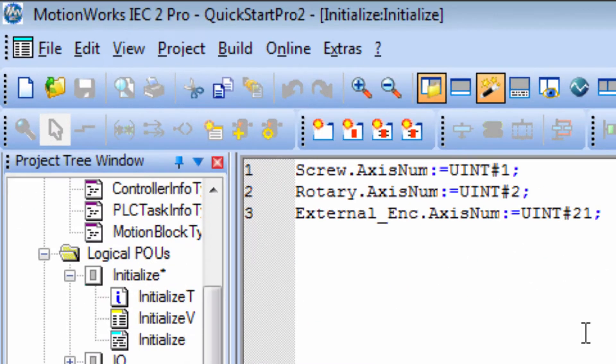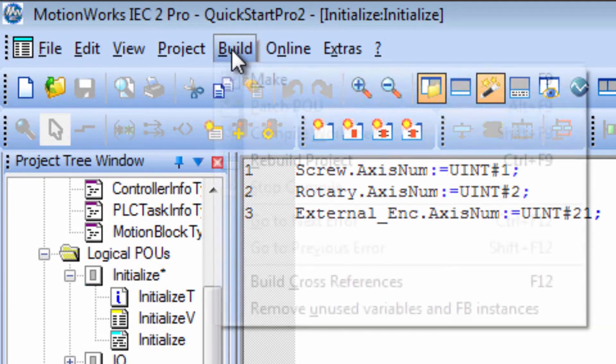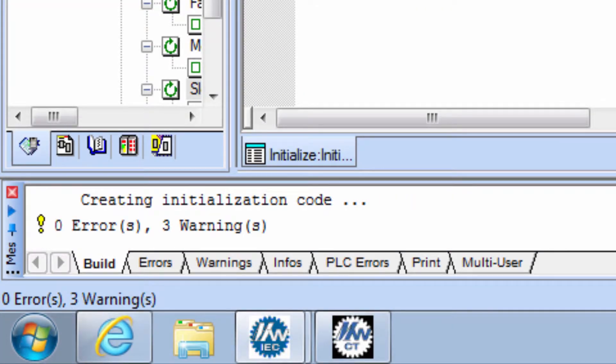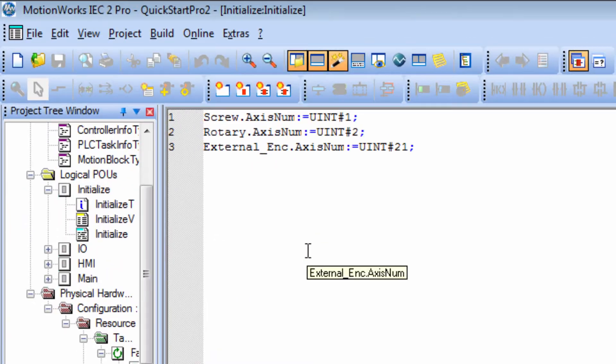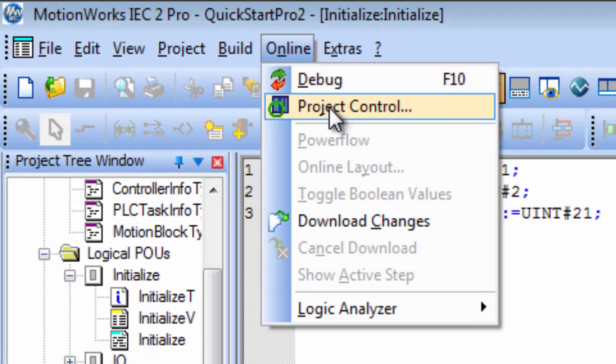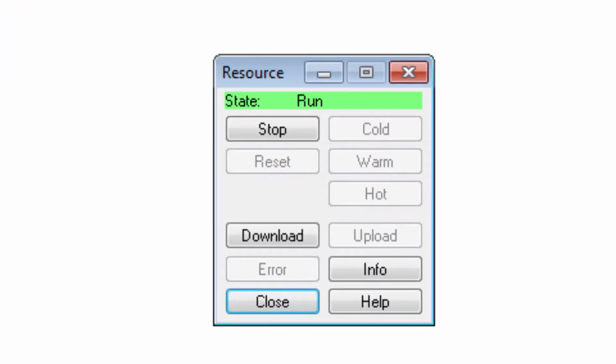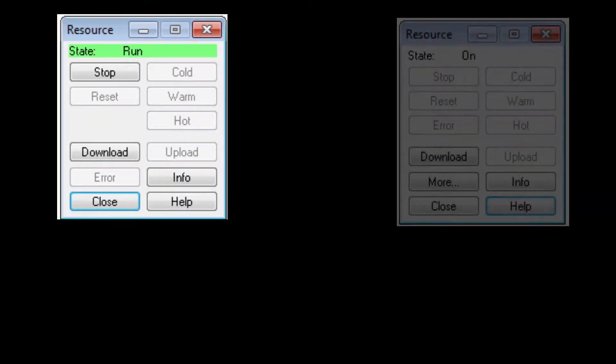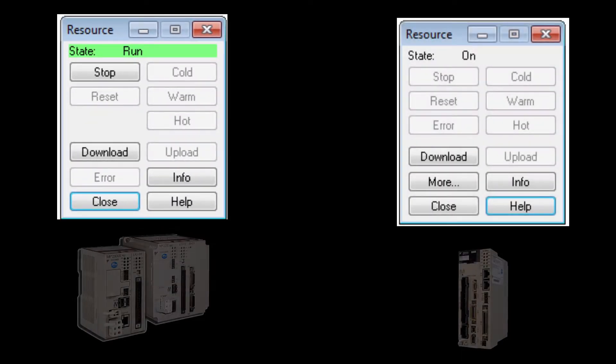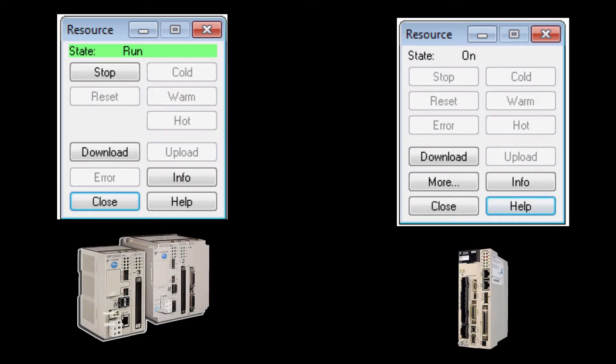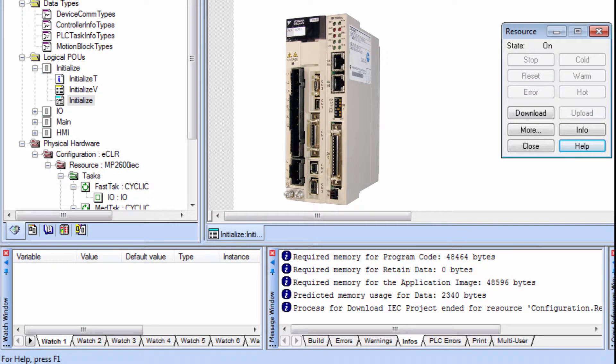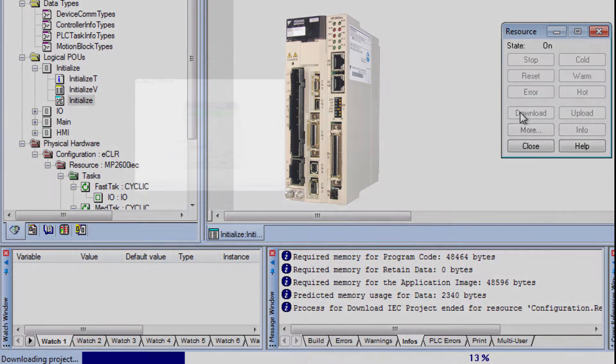Now to get this to run in the controller, first use the Make button. And after successful make, use Online Project Control to bring up the resource window. This window is slightly different between the MP2600 IEC and MP2300 IEC controllers. For the MP2600 IEC, just click Download.